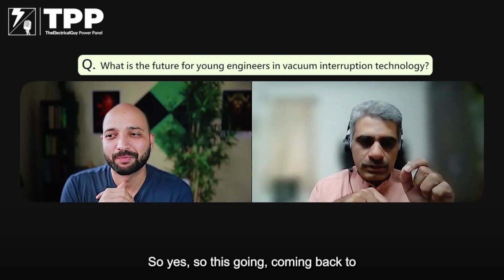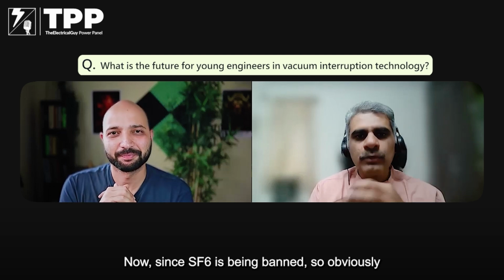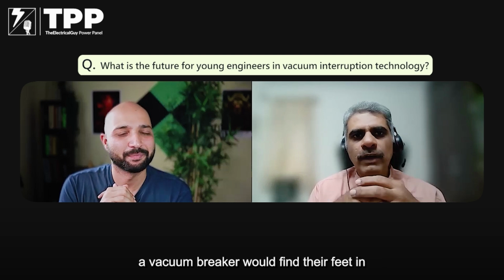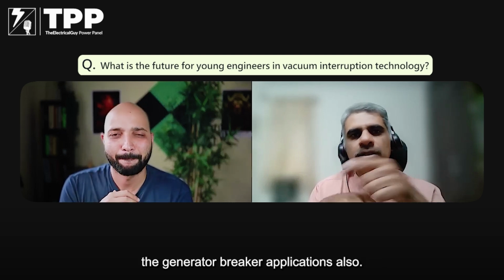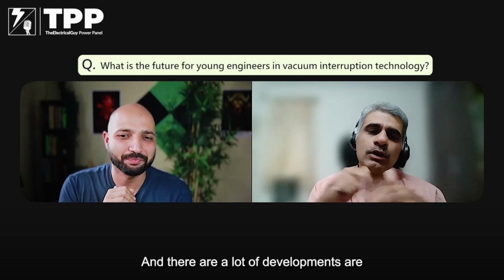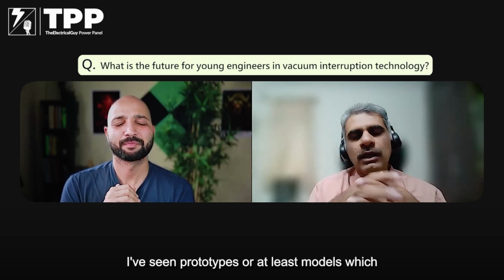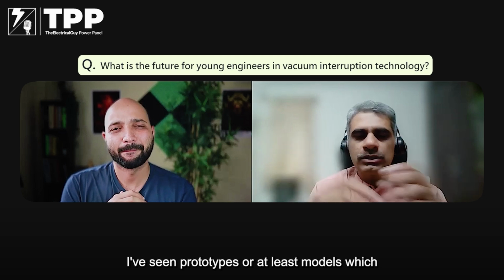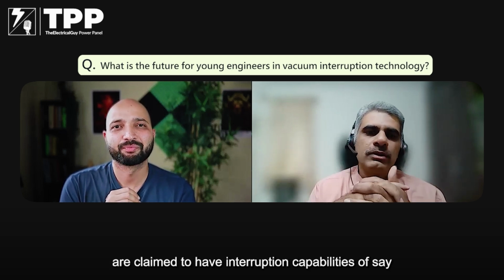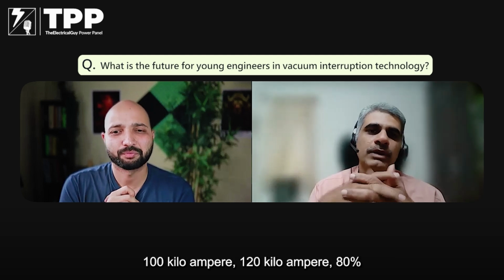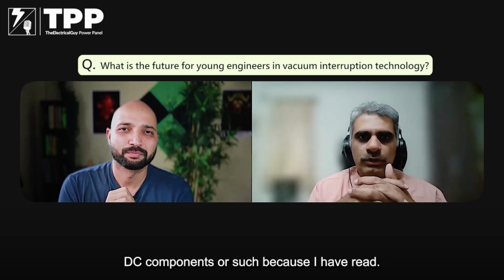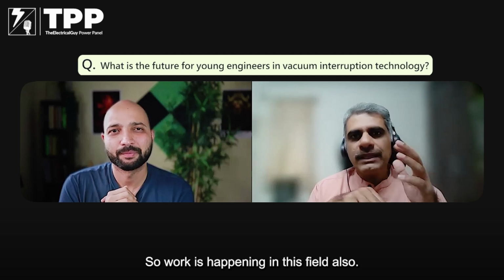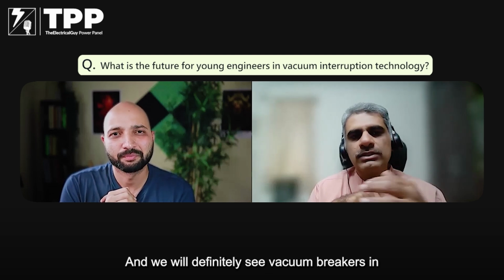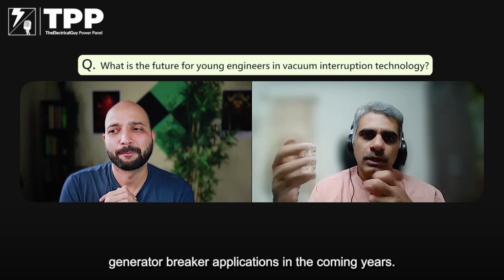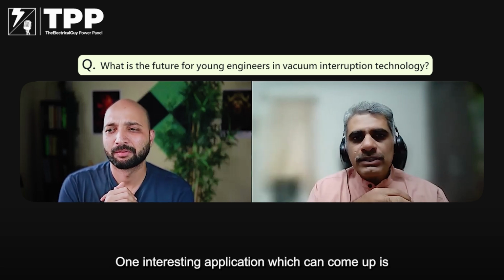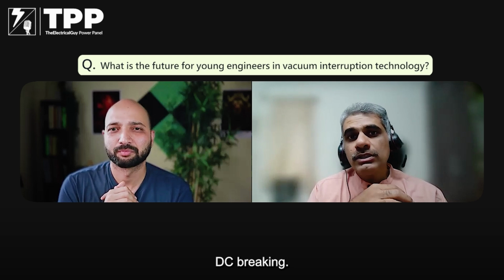So coming back to the generator breaker now, since SF6 is being banned, obviously vacuum breakers would find their feet in generator breaker applications also. And a lot of developments are required. Developments are being done. I've seen prototypes, or at least models, which are claimed to have interruption capabilities of say 100 kiloampere, 120 kiloampere, 80% DC components. Such figures I have read. So work is happening in this field also, and we would definitely see vacuum breakers in generator breaker applications in the coming years. One interesting application which can come up is DC breaking.